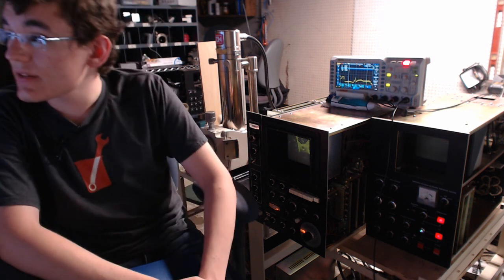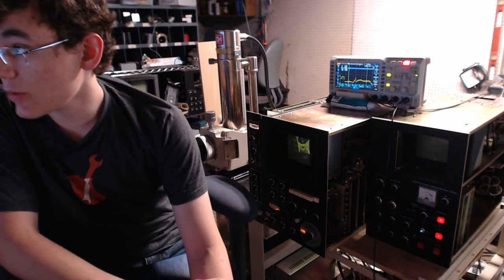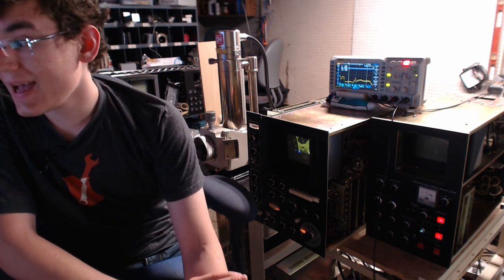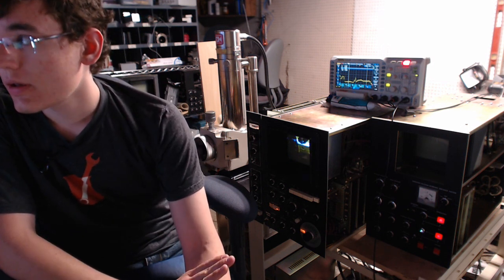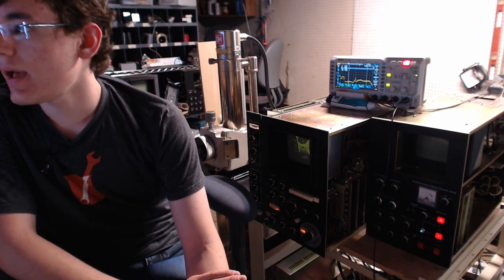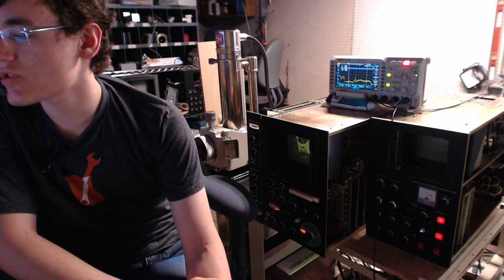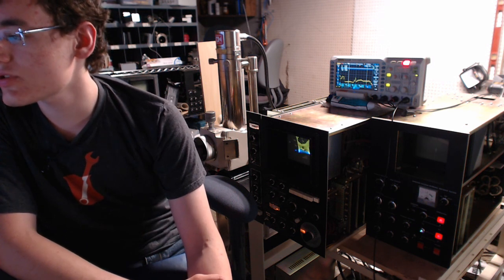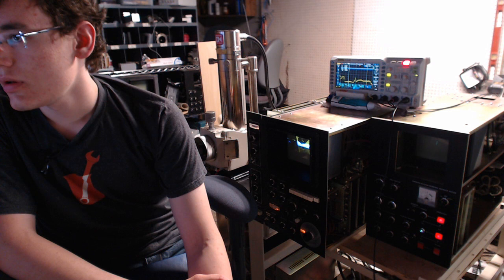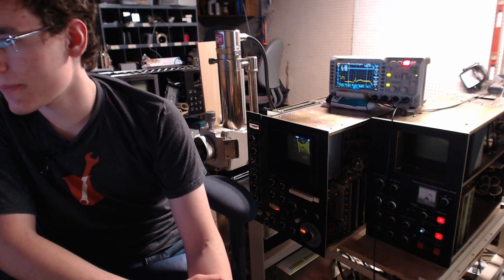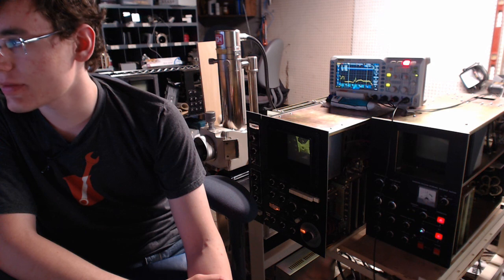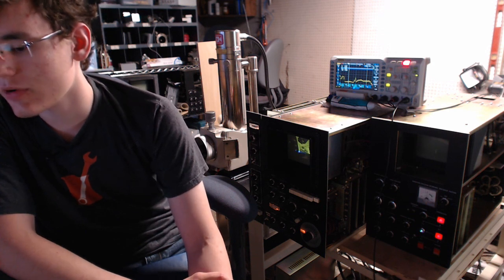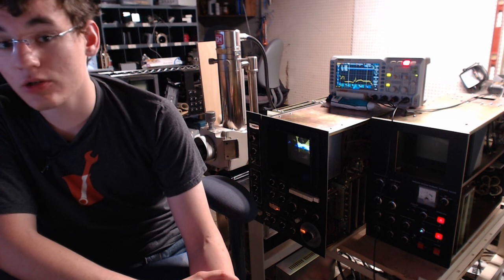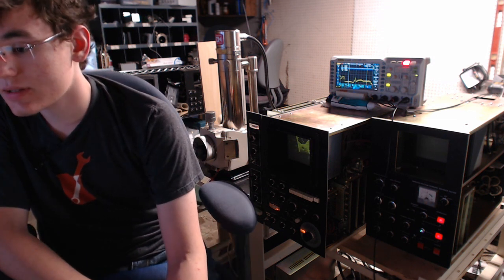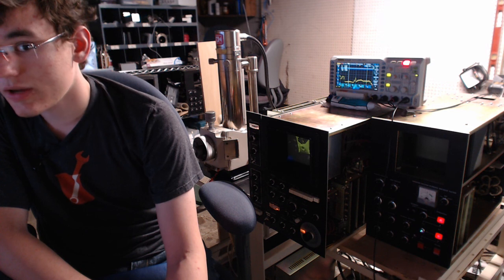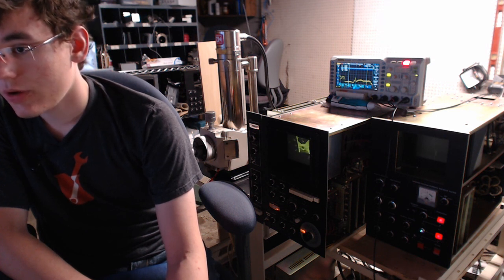No, so I can detect that 1 kilohertz pulse noise coming all the time, but it's only bad and only affecting image quality when the scintillator is on. And the noise becomes more visible when the bias is changed, but it doesn't change beyond just the magnitude, which is kind of expected. Oh, well, that actually rules out signal processing, because changing contrast doesn't change your signal processing at all. It only changes the photomultiplier, which is good.